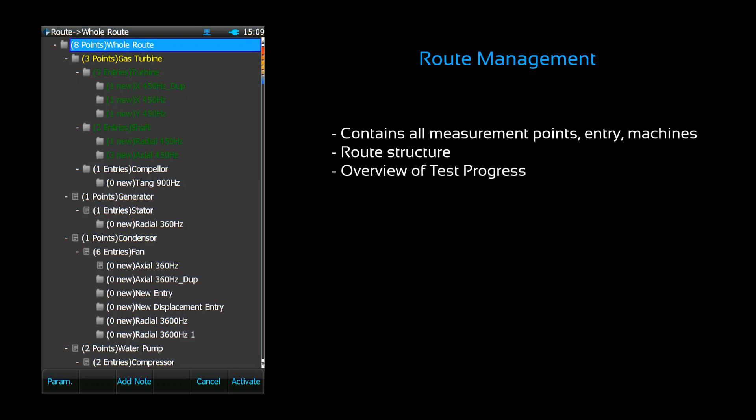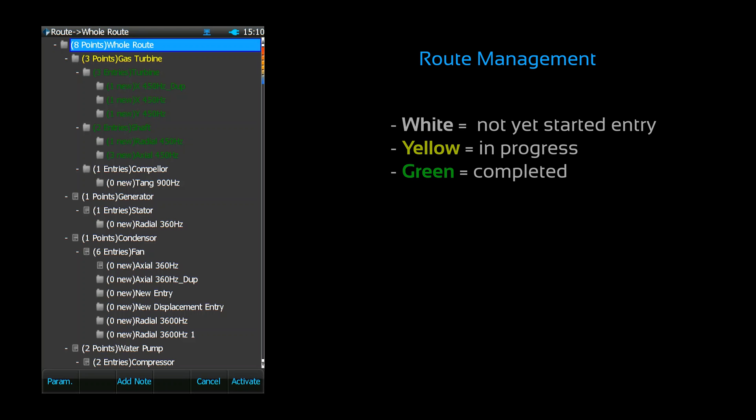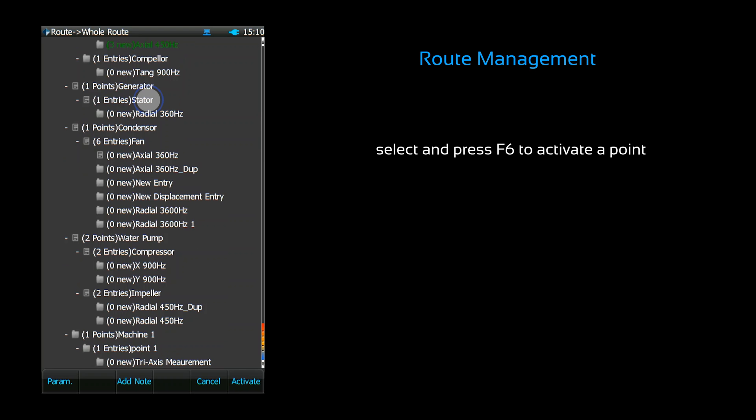The route display screen also serves as an overview of your testing progress. You can see the status of individual measurements based on the color of the entry. White entries have not yet been started, yellow entries are in progress, and green entries have already been completed. You can select and activate measurements from this list. Press F6 to activate a point, and it will take you to the signal display screen.